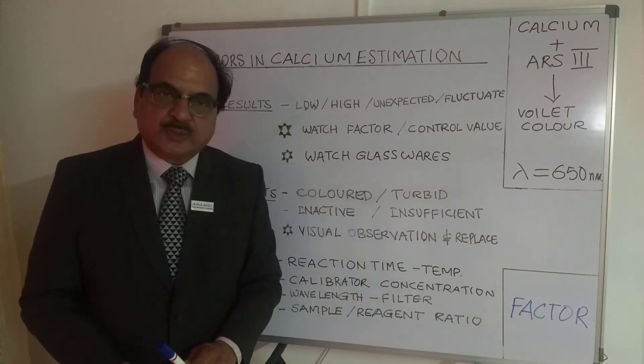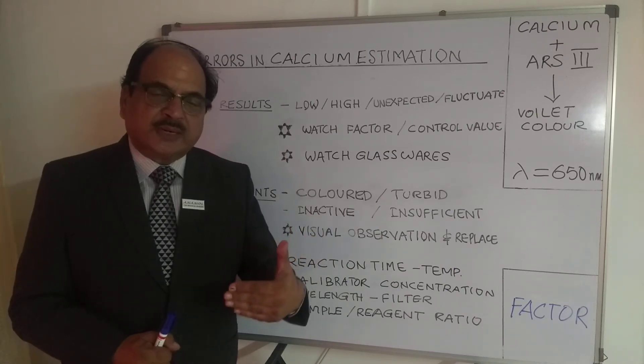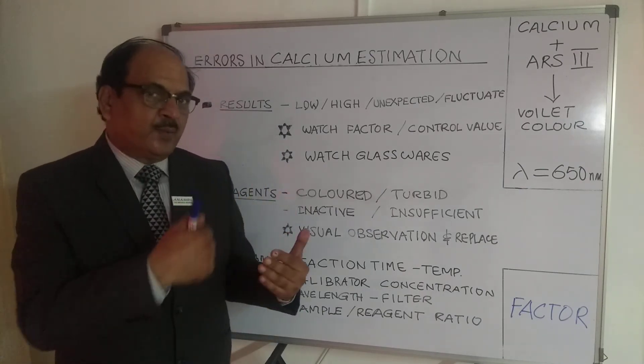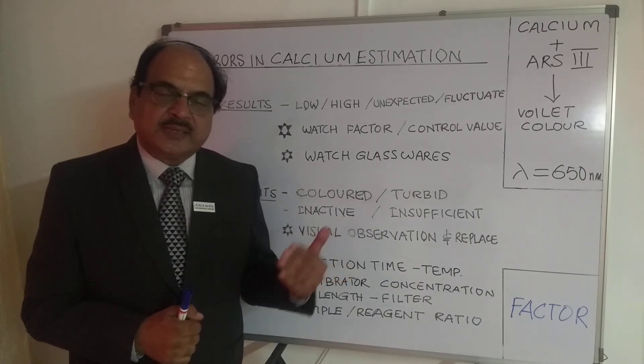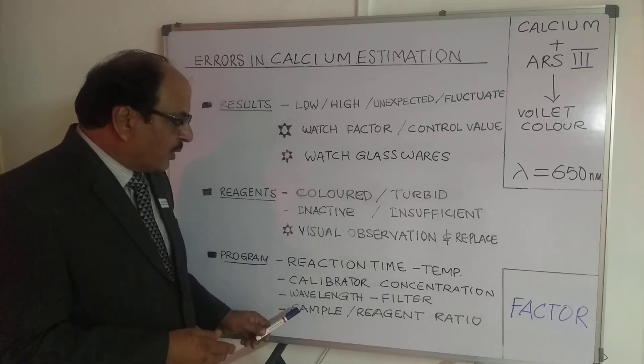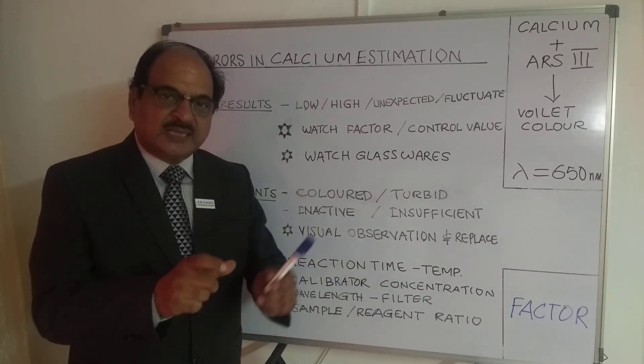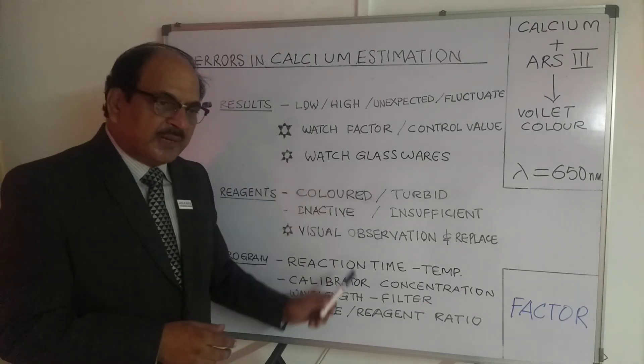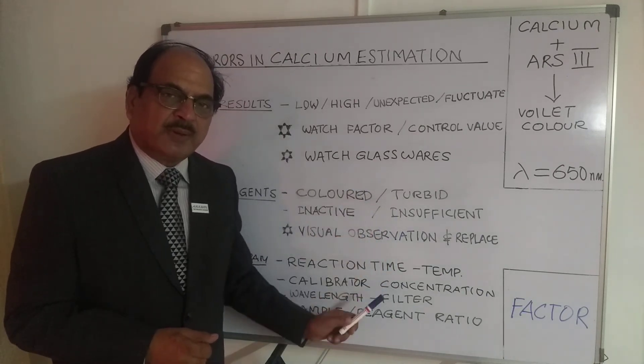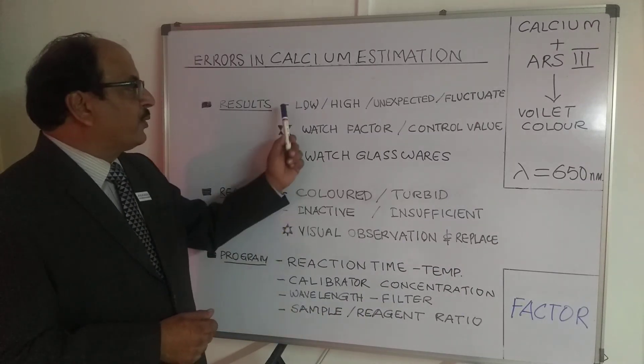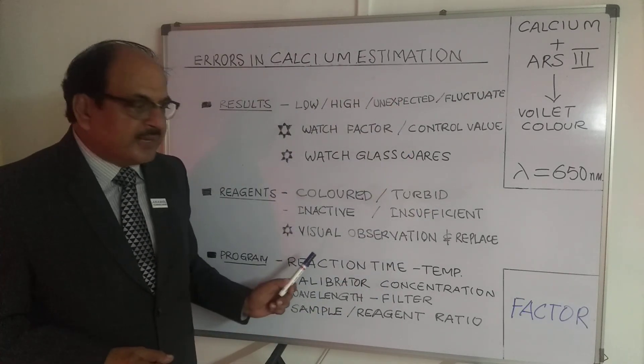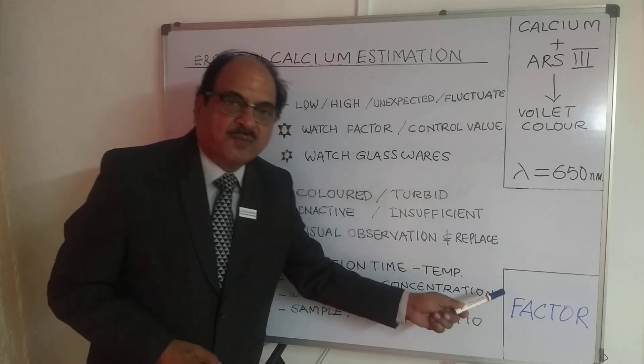Sample-to-reagent ratio is another important issue. The normally recommended ratio is 1 ml of reagent plus 20 microliters of sample. You can also use exactly half — 500 microliters of reagent and 10 microliters of sample — and it still gives good performance. However, whatever sample-to-reagent ratio you use, ensure that calibration is performed on the exact same ratio. If calibration and sample runs use the same ratio, there is a very high probability of getting accurate results.